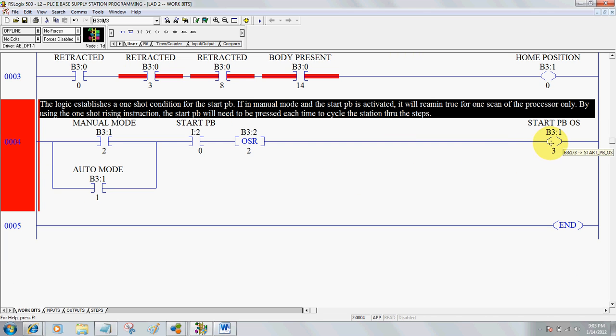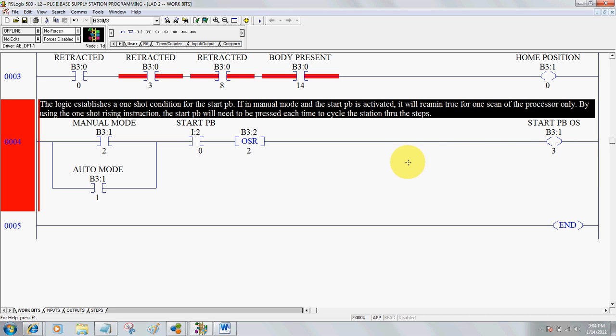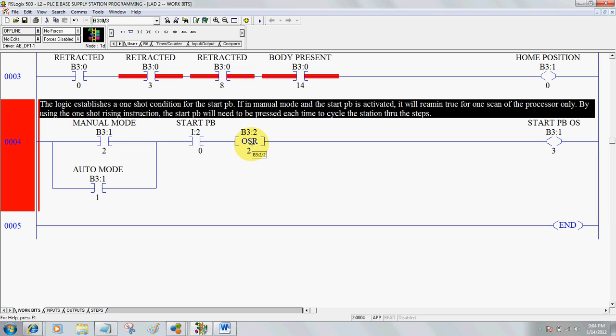Finally, to create a one-shot event to trigger a start condition, we need our start PB. In this logic, it's manual mode or auto mode with an initiation of the start PB. It's going to allow this one-shot rising bit to become true for one program scan only. If you hold the button, this instruction would only become true one time — you must release the button and press it again to get another initiation of the start PB. That's the purpose of a one-shot rising bit: the preceding conditions must be true, then this instruction becomes true for one program scan only.